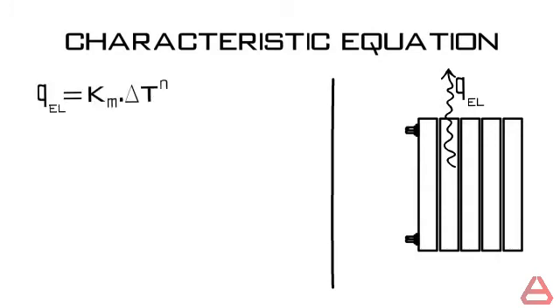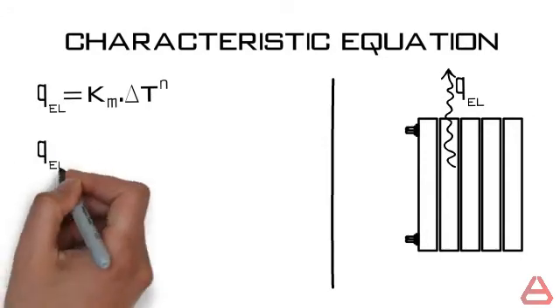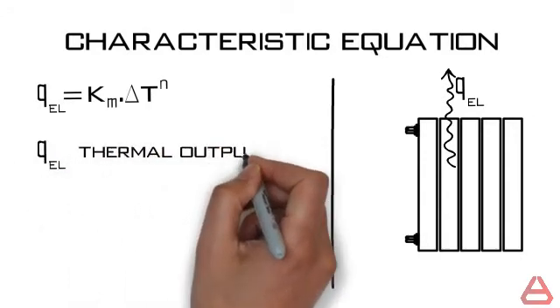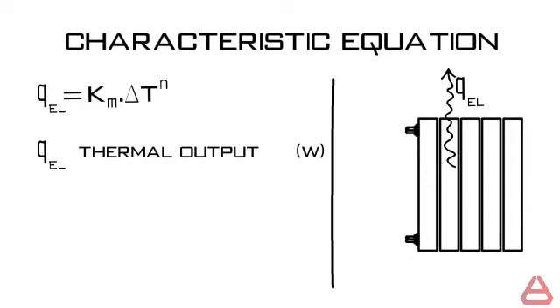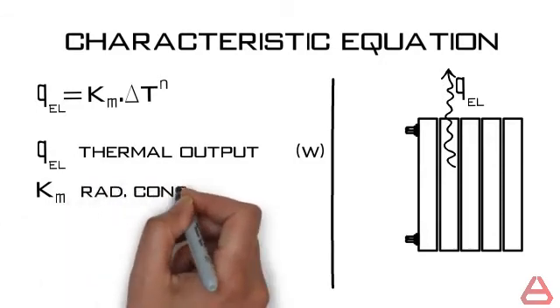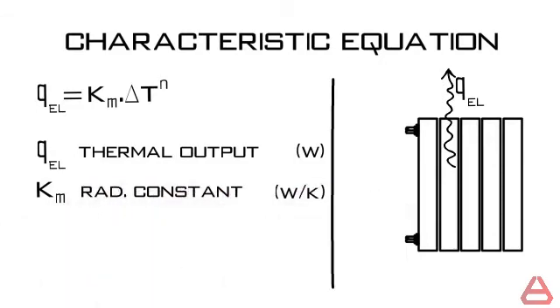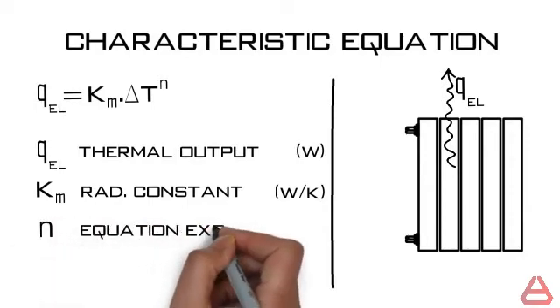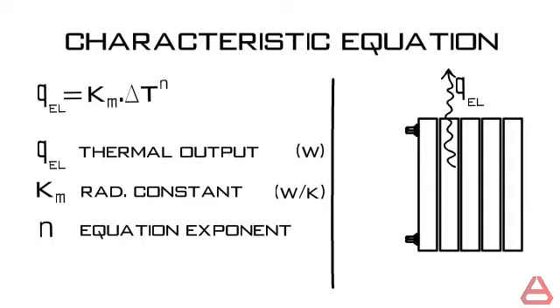Q element is equal to Km multiplied by delta T to the power n. Q element is the thermal heat output generated by the radiator element in watts. Km is the characteristic constant of the radiator in watts per Kelvin. And n is the characteristic exponent of the equation due to the ratio of convection to radiation thermal output.